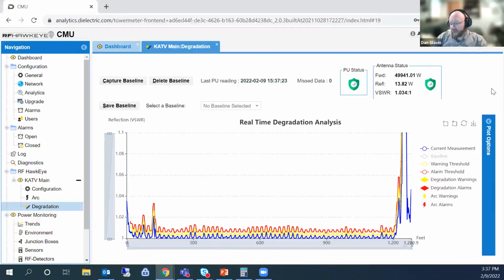The yellow line here is a warning threshold, as you can see in the legend on the right-hand side, and that's a user-defined threshold. So if you know how your system should operate - maybe in the summer it operates at a low VSWR, but then you get some icing over the winter and it elevates a little bit, but you've known it to be not an issue - you can set your threshold there.